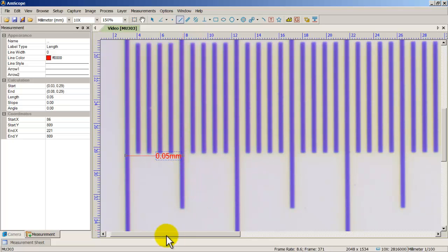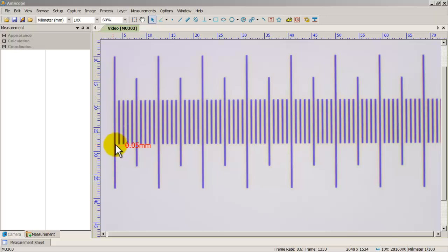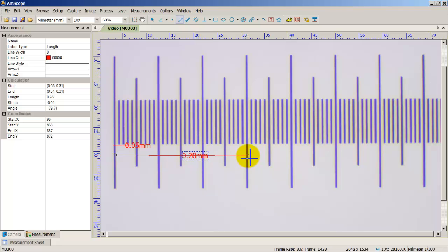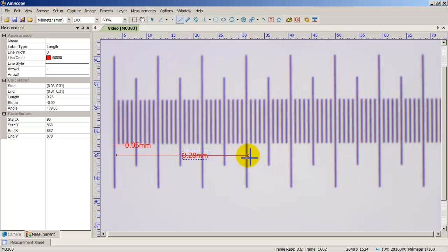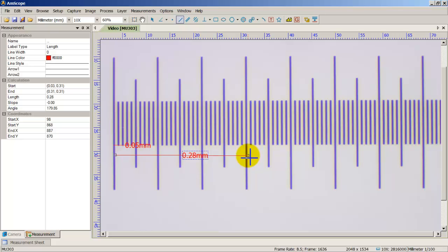So I measured 0.05 and it's accurate. Let me grab the line again and measure another span — making sure the line is straight with no breaks — and that comes out to 0.28. This is how you do measurements and calibration on the microscope. For each individual objective you'll need to calibrate separately, so just follow these steps and you should be fine. If you have any questions, comment below — I'll include links to the software, the camera, and the microscope I was using. That's pretty much it, you guys have a good one!